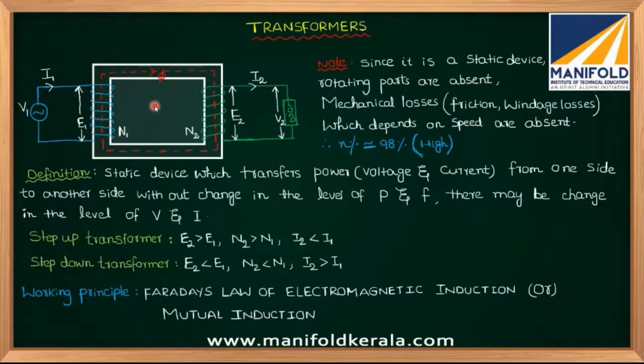D. Very good, that means yes. The correct nomenclature for windings in a transformer is low voltage winding and high voltage winding, because without connecting source and load, it is not possible to justify which one is primary and which one is secondary. Is it clear? No doubt, in our discussion we will be using primary winding and secondary winding, but from the examination point of view, please go for option D, low voltage winding and high voltage winding, not primary winding and secondary winding.